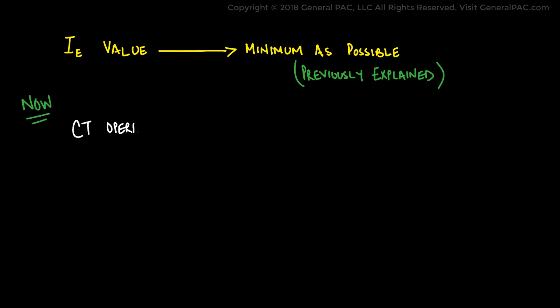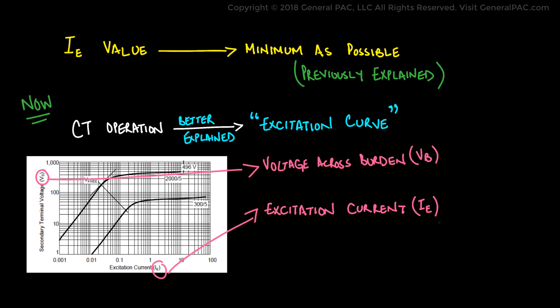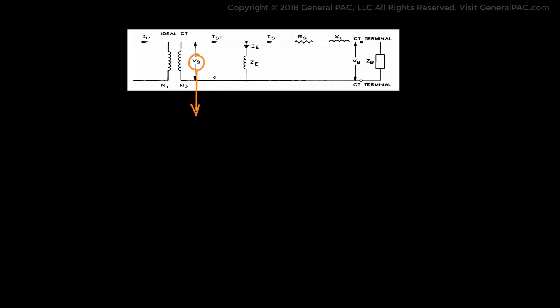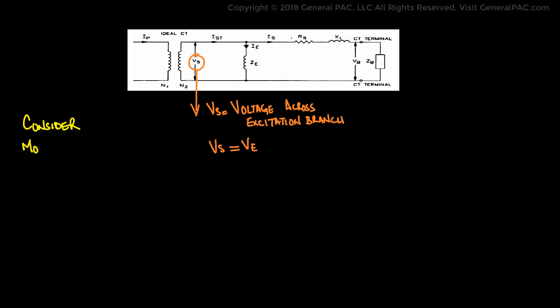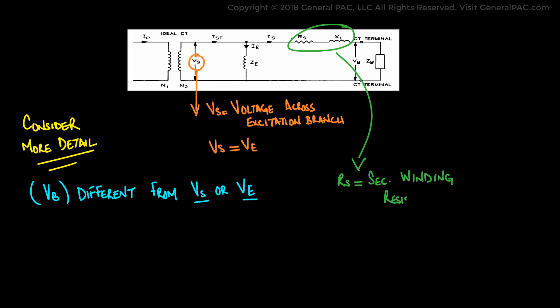The CT operation can be easily explained by the excitation curve. This curve shows the relationship between the voltage across the burden and the excitation current. Vs is the voltage across the excitation branch as pointed out by this diagram, and also sometimes described as VE. Keep in mind that the voltage across the burden is Vb, and there is a difference between the voltage across the excitation branch Vs and the voltage across the burden. The difference comes from the secondary winding resistance RS and leakage reactance XL — that's how we're modeling it.